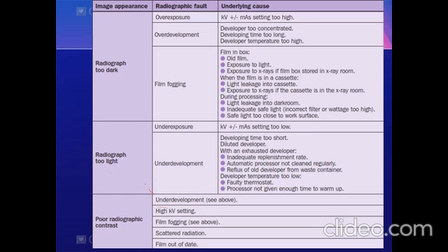So, if the appearance is too dark, it could be overexposed or overdeveloped. Medyo natagal yung pag-expose natin, longer time, or natagalan sa developer. Pwede rin caused by film fog. Film fog due to light, chemicals, aging, radiation.